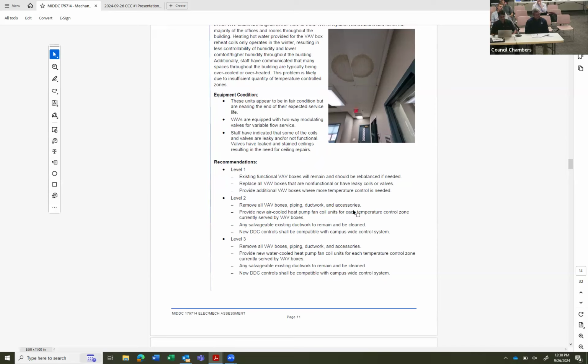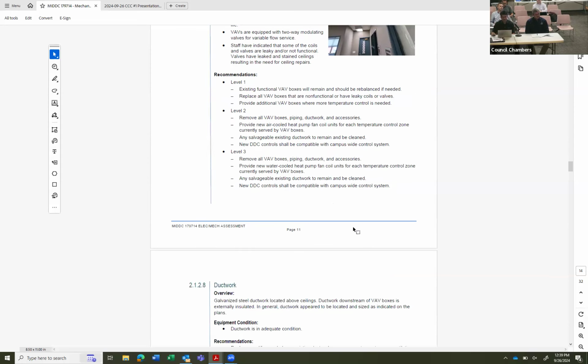Level 2, all the VAV boxes would be removed and essentially replaced with the VRF fan coil units, and we would also provide probably additional units to have any number of desired zones throughout the building. And again, in this scenario we would try to reuse whatever ductwork we could to reconnect those new fan coil units to them. And for the level 3, the geothermal option, we would be removing all the VAV boxes, and we'd be providing new fan coils that would be connected to this geothermal hydronic system. And again, we'd salvage what ductwork we could.